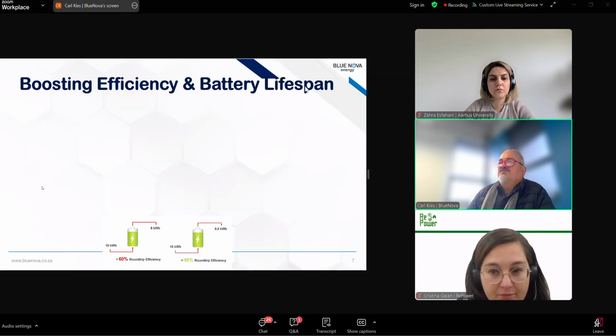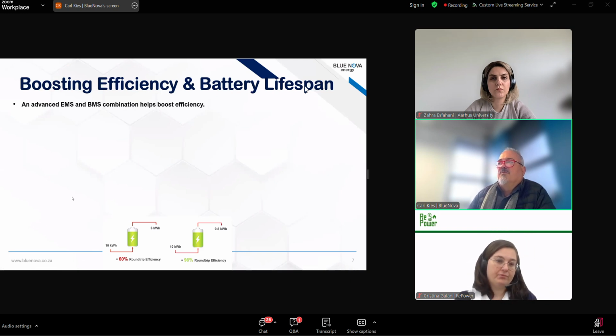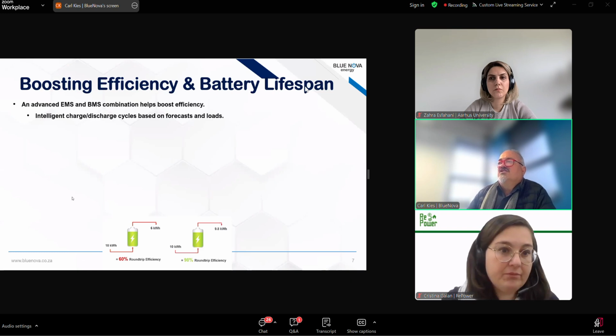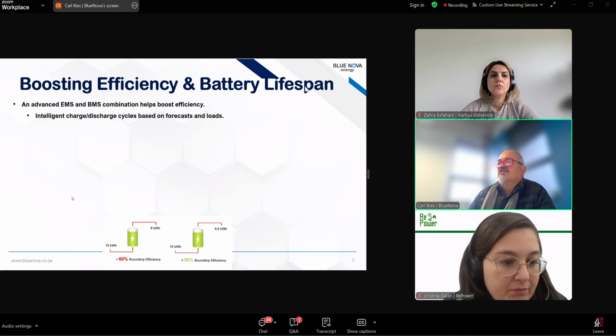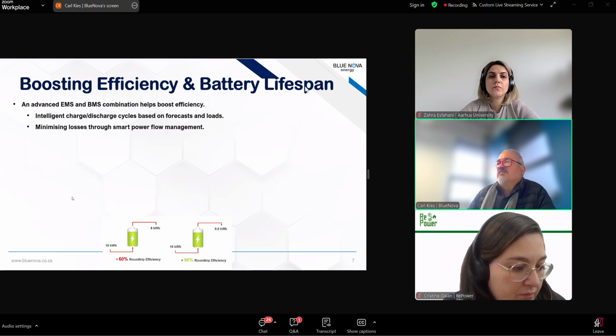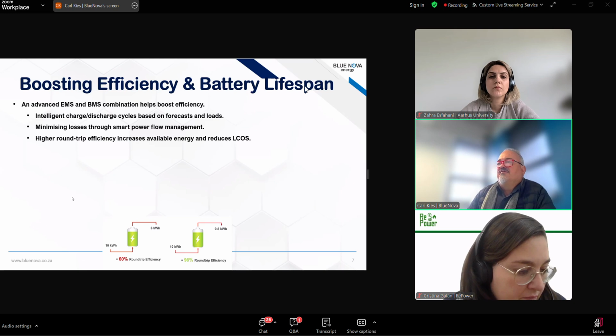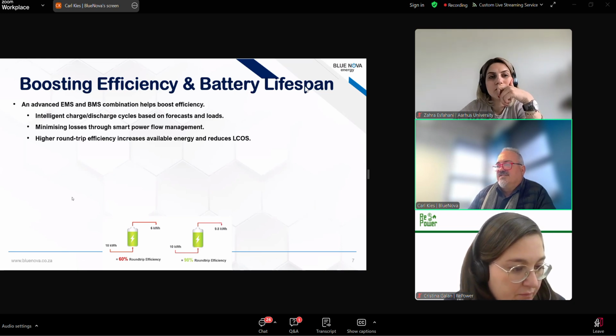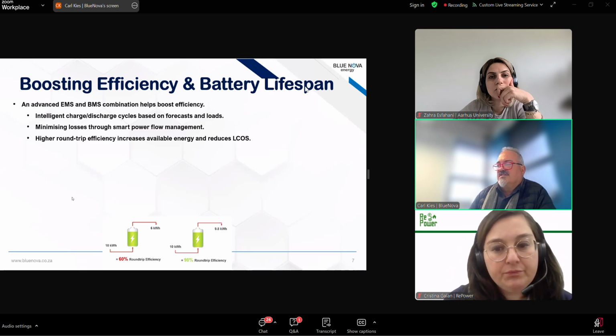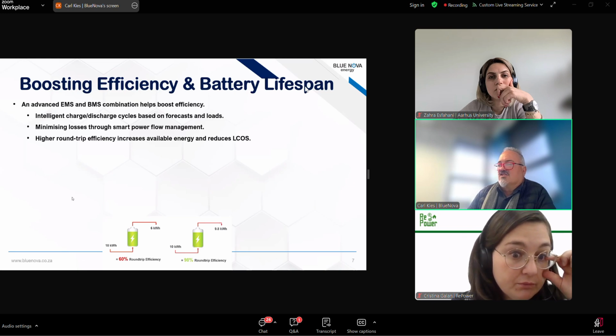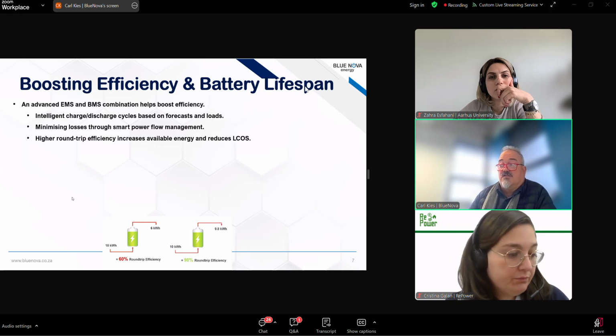As we already saw, boosting efficiency and lifespan is important from an investment optimization point of view. A good EMS-BMS combination will help boost that efficiency, with intelligent charge and discharge cycles based on forecasts and loads, and minimizing losses through power flow management. You get higher round-trip efficiency, which increases availability and reduces cost. The simple difference between a 60% round-trip efficiency and a 98% round-trip efficiency is that for every 10 kilowatt hours you charge into the system, one case gives you only 6 kilowatt hours of usable energy, whereas the other gives you 9.8 kilowatt hours - a massive difference.